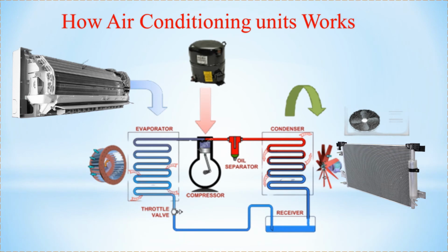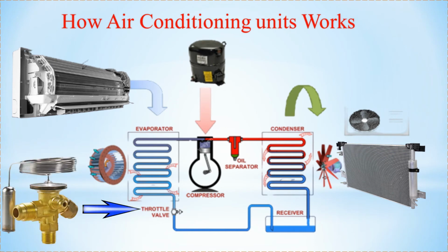As the air conditioner runs, the compressor pulls cold, low pressure liquid refrigerant through the tubing in the evaporator coil. Before entering the evaporator coil, the refrigerant passes through the expansion valve, or we can say the expansion device. These valves relieve the pressure from the liquid refrigerant, which rapidly cools it, or we can say the temperature of the refrigerant suddenly decreases. The liquid refrigerant leaving the expansion valve is quite cold, which is what allows it to absorb heat from the air. The expansion valve also controls exactly how much refrigerant flows to the evaporator.